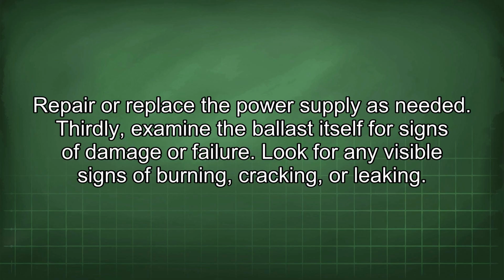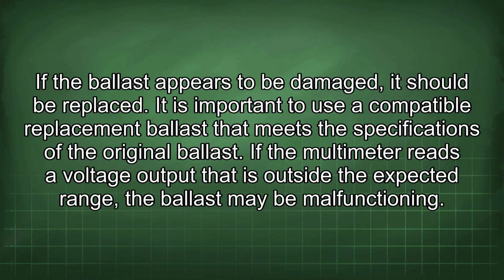Thirdly, examine the ballast itself for signs of damage or failure. Look for any visible signs of burning, cracking, or leaking. If the ballast appears to be damaged, it should be replaced. It is important to use a compatible replacement ballast that meets the specifications of the original ballast.